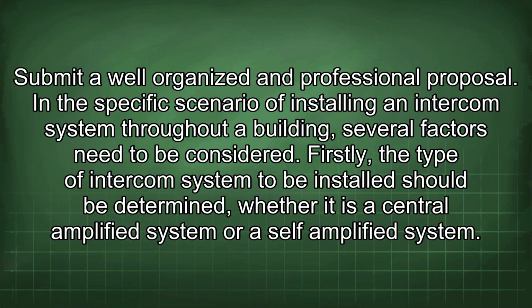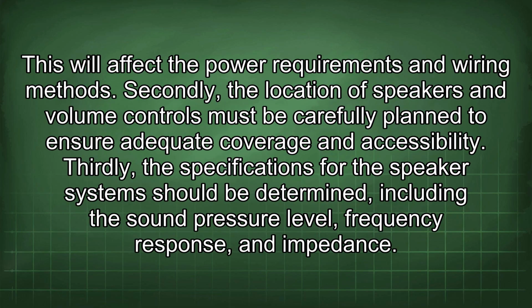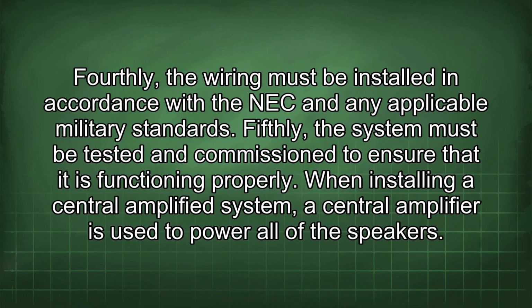In the specific scenario of installing an intercom system throughout a building, several factors need to be considered. Firstly, the type of intercom system to be installed should be determined, whether it is a central amplified system or a self-amplified system. This will affect the power requirements and wiring methods. Secondly, the location of speakers and volume controls must be carefully planned to ensure adequate coverage and accessibility. Thirdly, the specifications for the speaker system should be determined, including the sound pressure level, frequency response, and impedance. Fourthly, the wiring must be installed in accordance with the NEC and any applicable military standards. Fifthly, the system must be tested and commissioned to ensure that it is functioning properly.